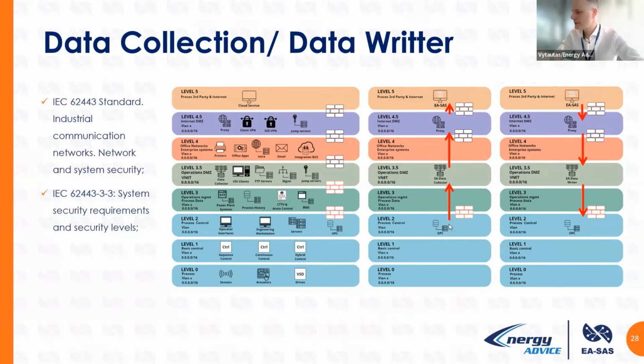And what we do, we install OPC. You have OPC. At your workstation level, SCADA level, we install Energy Advice data collection software, which is capable of working only one way, to read data from OPC, or in some cases from the controller. So it only reads data. Of course, this connection has a firewall. This is the firewall sign. And from the data collection software and proxy server, we deliver data to the cloud. When we write commands back from the cloud, optimization commands, we write back through an absolutely different path. It's another route, another channel. We deliver commands each minute to the proxy, to the data writer software, and the writer software puts the data to the OPC box. And with OPC, of course, we send commands to the PLC.